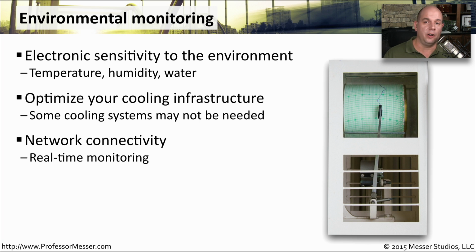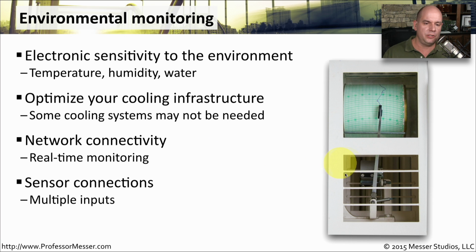Our temperature and environmental monitors are usually not one of these older analog devices. They're usually a newer digital device, and we're connecting it up with Ethernet, and we're connecting back to central monitoring tools that can provide us with alarming and alerting. We also generally see multiple sensor components, not just a single bar that's going across a piece of paper. It usually has many different types of sensors connecting to many different parts of the organization, and all of that information is consolidated back to one central environmental device, which then reports back to us.